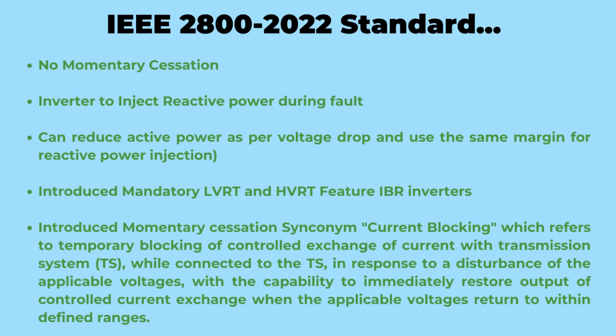Hold on to your seats as we unveil the exhilarating requirements mandated by the IEEE 2800 standard for inverter-based resources. First and foremost, say goodbye to momentary cessation. The IEEE 2800 standard prohibits the use of momentary cessation in IBRs, ensuring a continuous and uninterrupted flow of power. But that's not all. IBRs are now required to inject reactive power during faults, enhancing the stability and reliability of the power system. Furthermore, these remarkable inverters have the capability to dynamically adjust their active power output in response to voltage drops, while utilizing the available margin to inject reactive power.